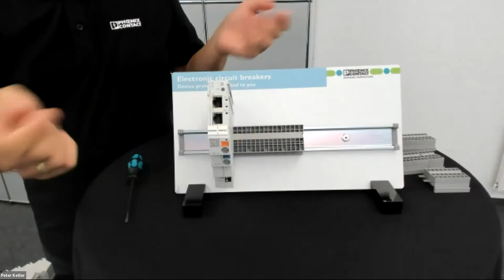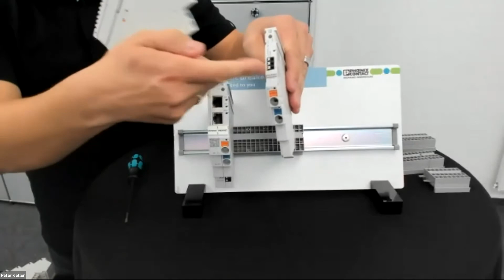In addition, we have two different additional power modules. First, the status reset module, where you get a status output if everything works fine in the system. We have a reset input for remote reset, and an 80% pre-warning. We also have the possibility to connect the IO-Link connection to get the data via IO-Link instead of Profinet, using a second interface.